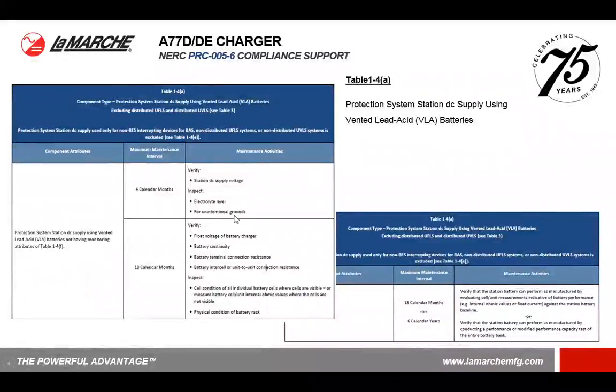Within PRC-005-6, there are different maintenance tables that come up depending on the type of battery that you're using. In this case, a vented lead acid battery is on table 1-4a. This maintenance table specifically refers to batteries not having monitoring attributes. So essentially at 4 months, someone would have to go visit this site to monitor the station supply voltage, the electrolyte level, and check for unintentional grounds.